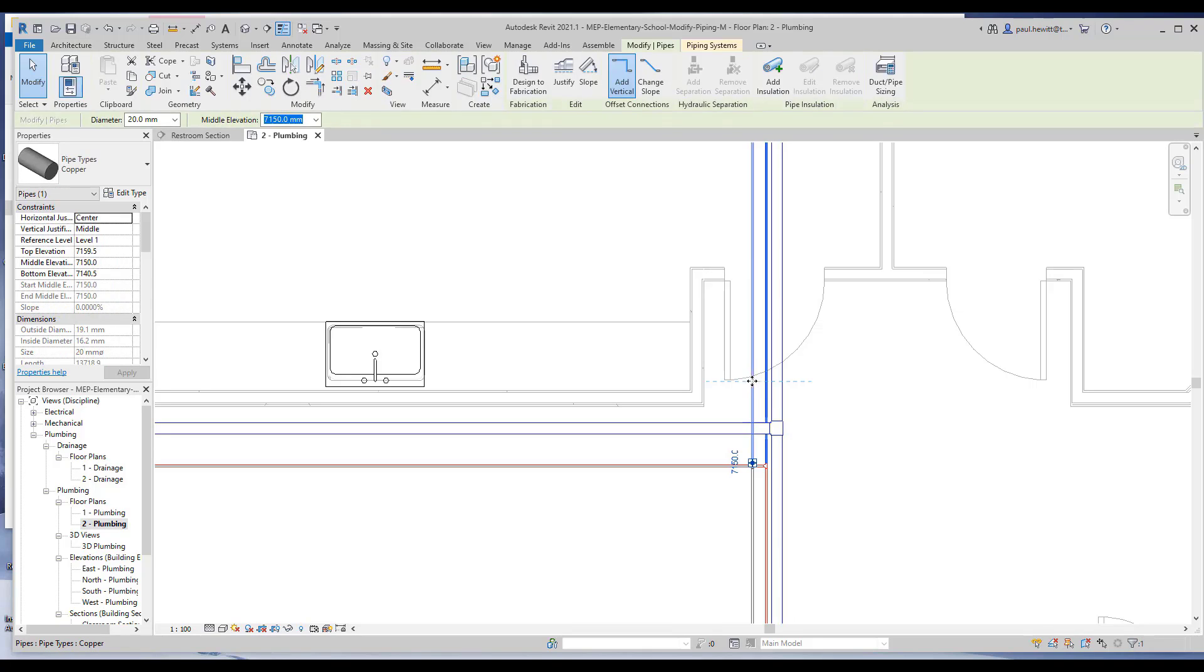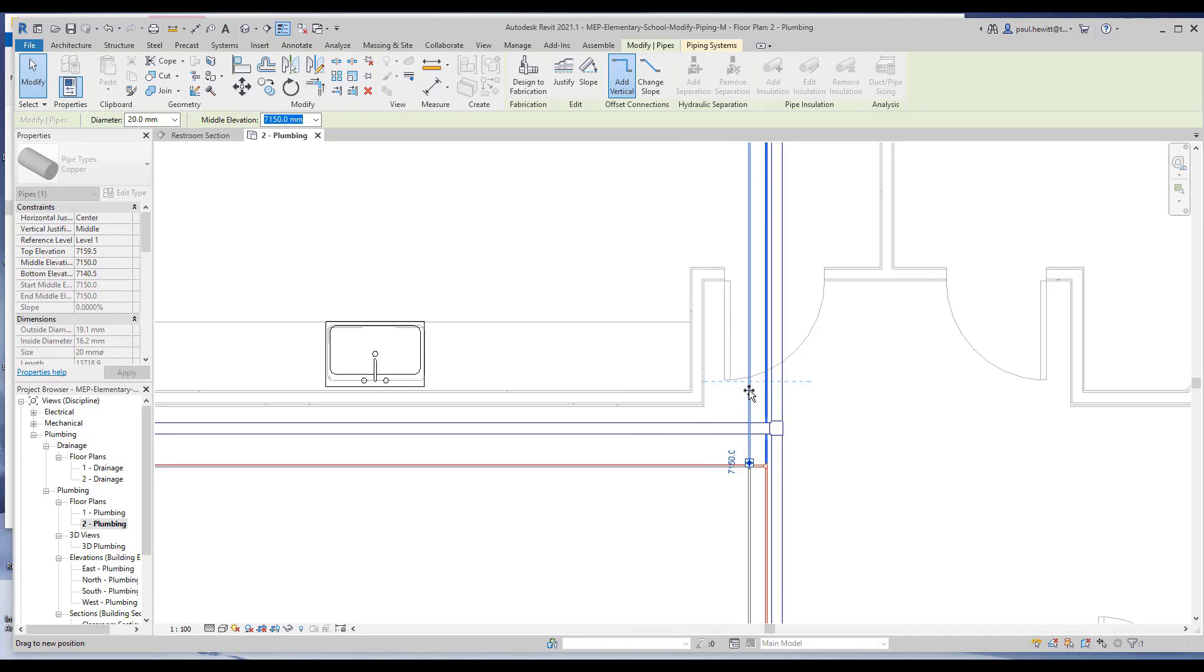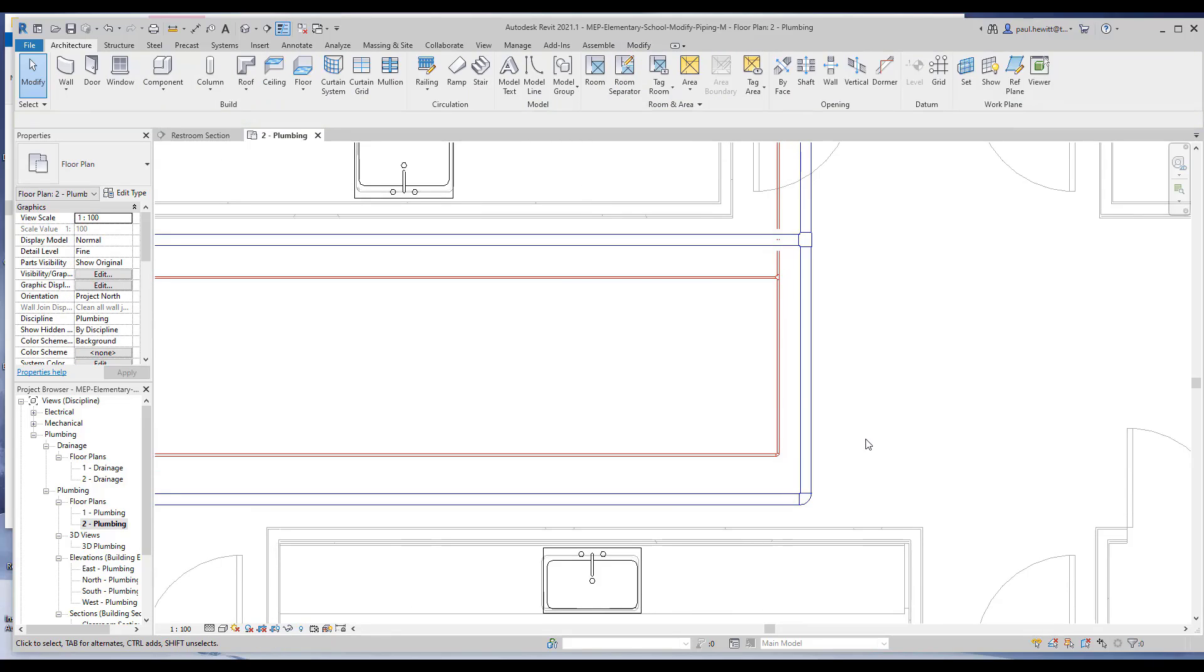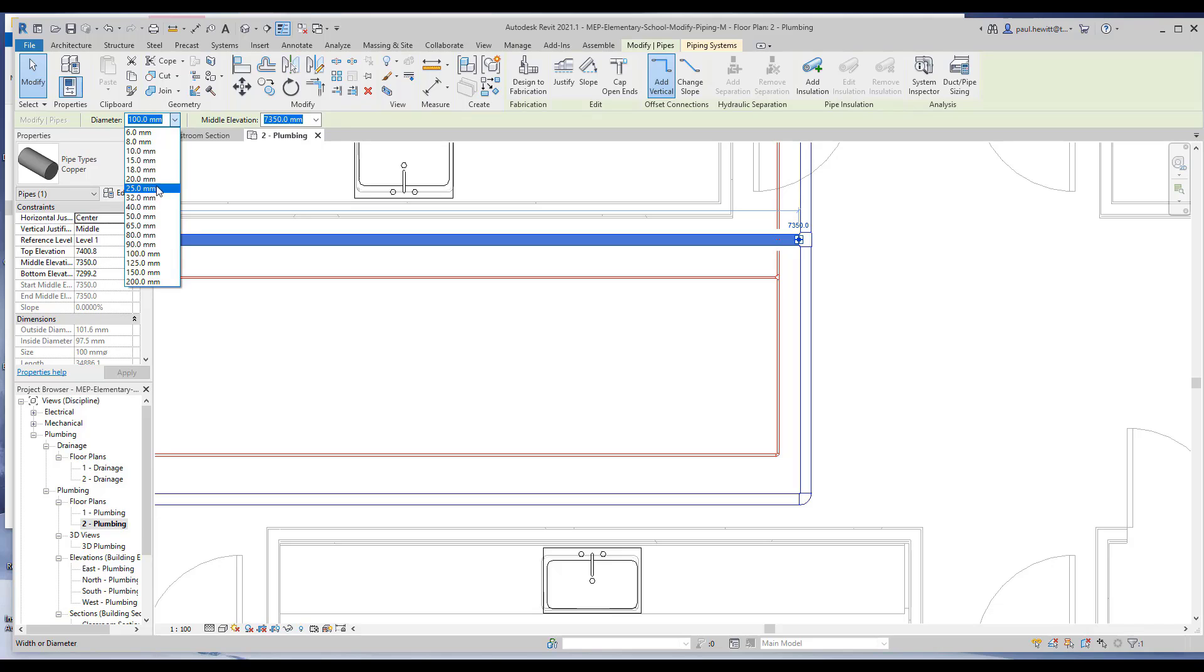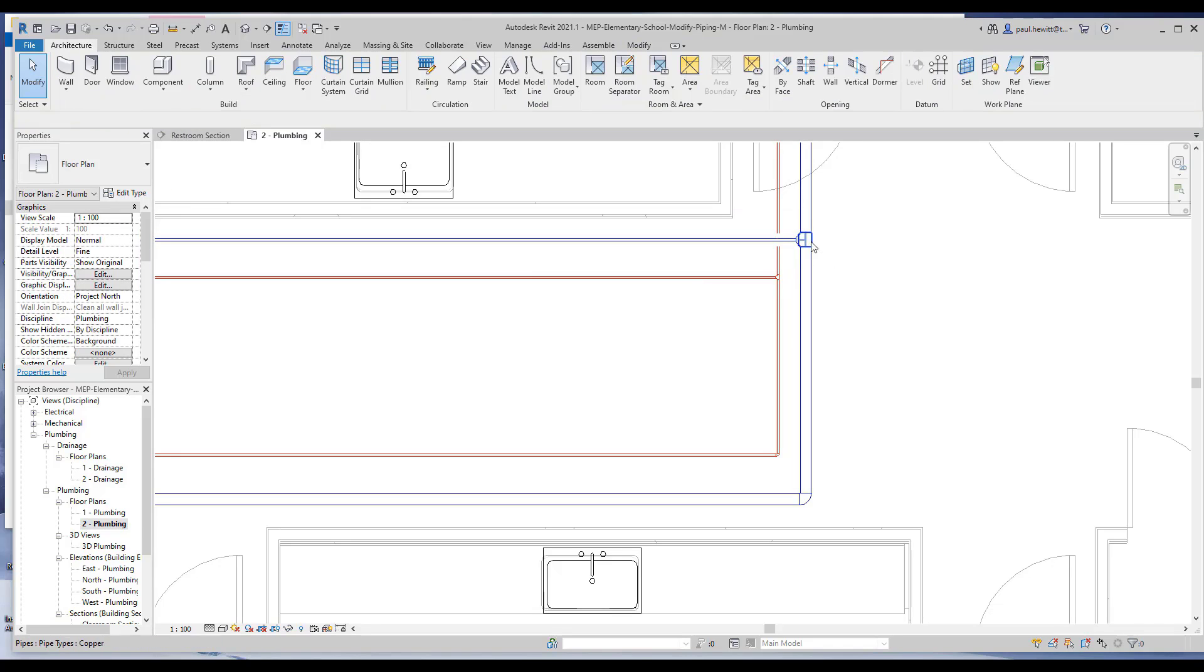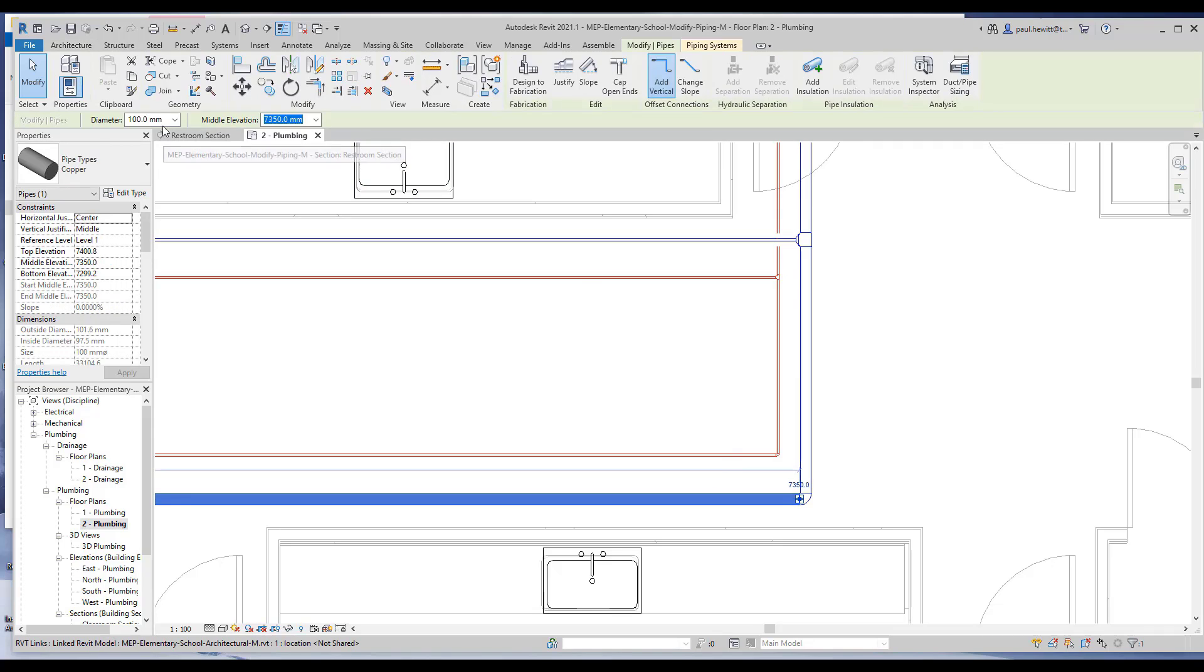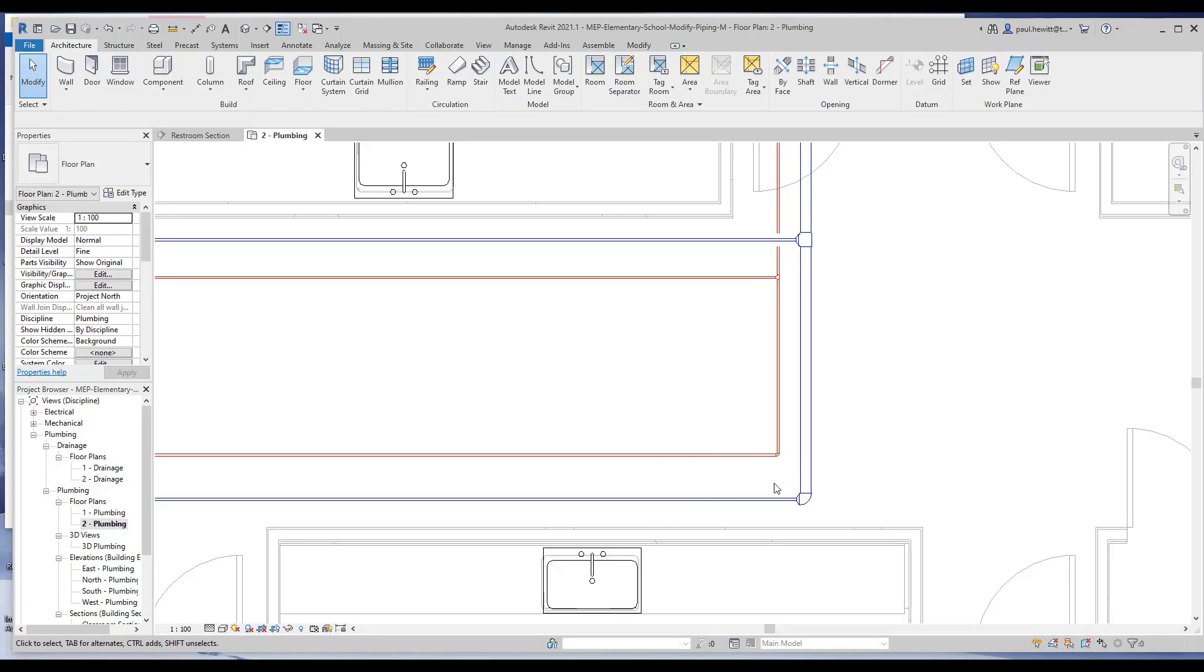Now we can easily just move a pipe, and it'll stay connected just by picking and dragging. We could also select a pipe and change size. So we can see here, we've got the 100 mil piping where we could do with just 25 mil. So let's select that and change that to 25 mil. The nice thing is where it's connected, it'll just actually put a transition in for us. Do the second part. And there's the transition again.